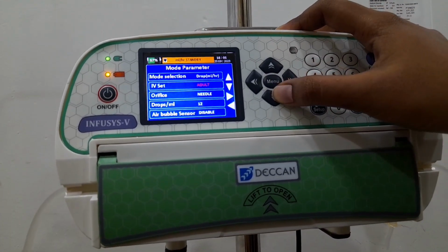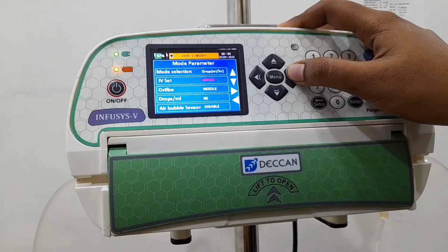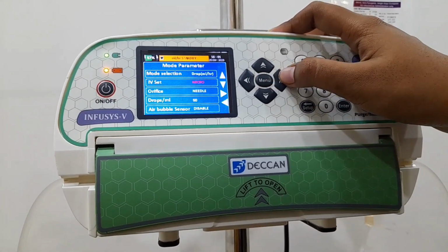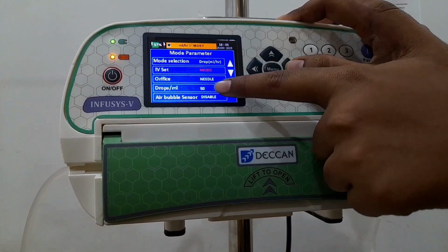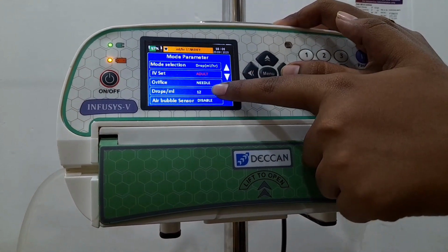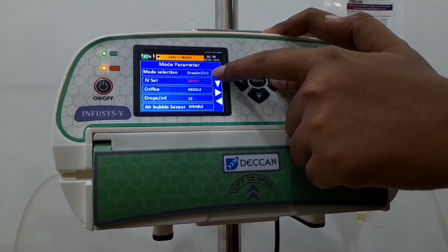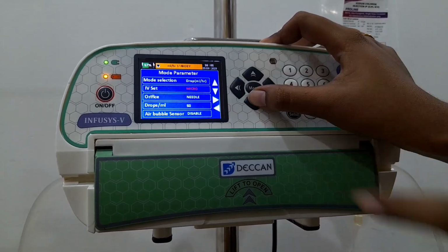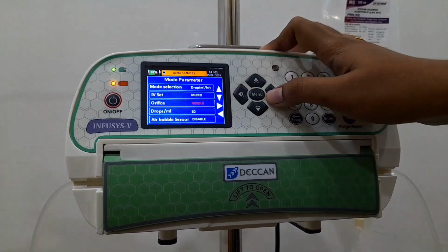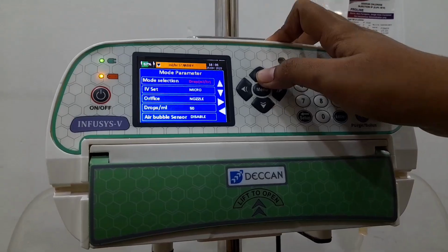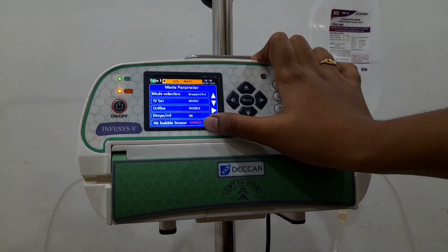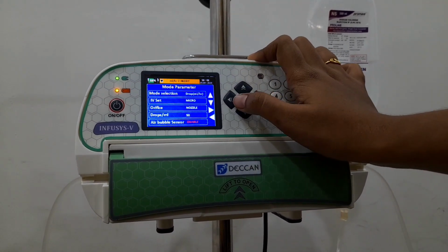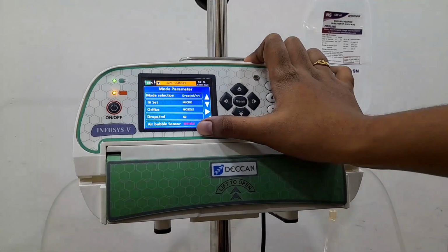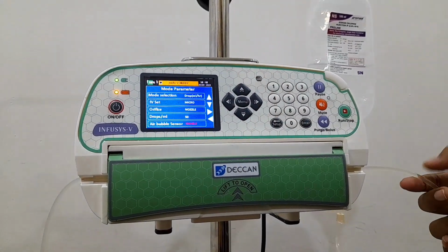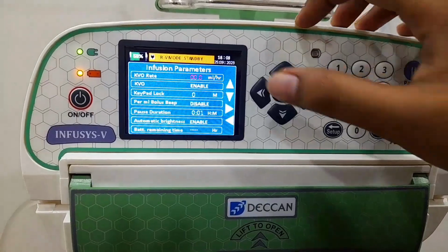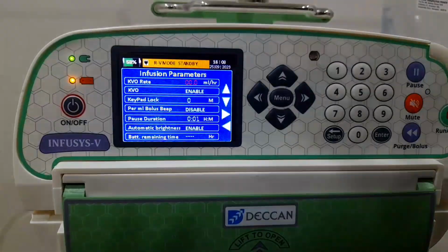In drops ml per hour, based on the IV set, adult and micro, the drops per ml get changed. For micro, it shows 60 drops per ml, and for adult it shows 12 drops per ml. And for orifice, we can change the orifice to nozzle or needle. The air bubble sensor is enabled, so if any air bubbles occur in the IV set, we get an alarm through that. Next, we can move to the infusion parameters.